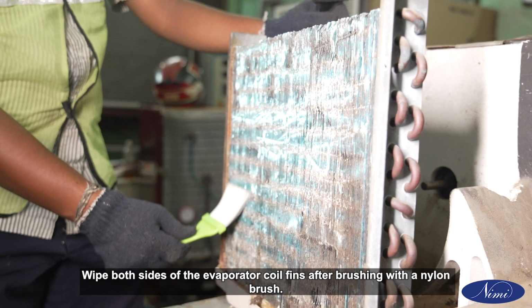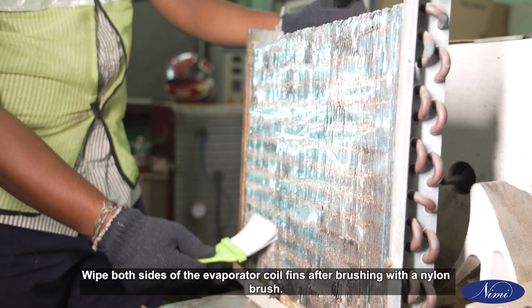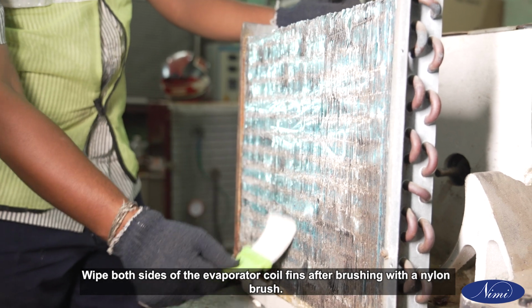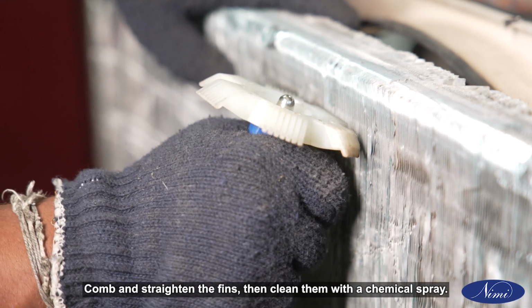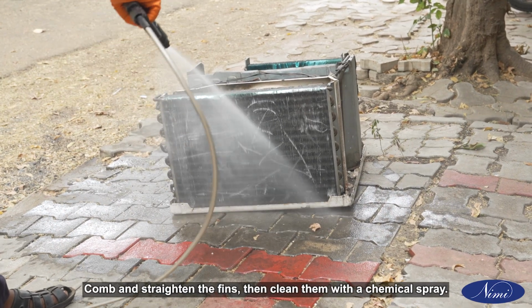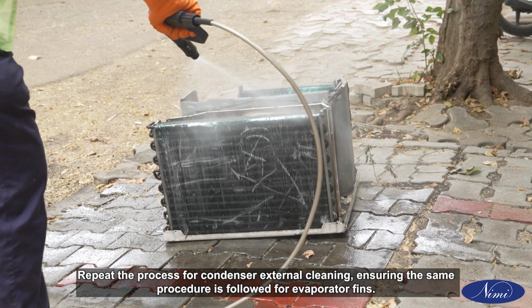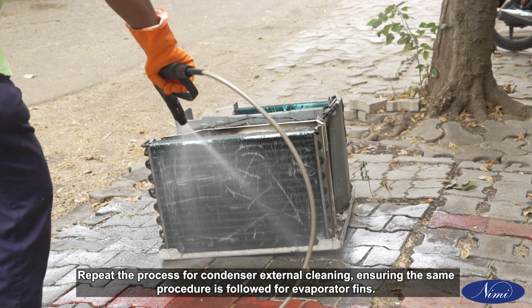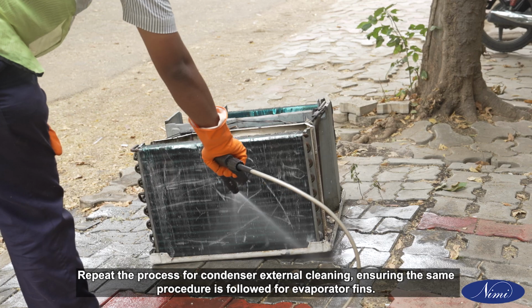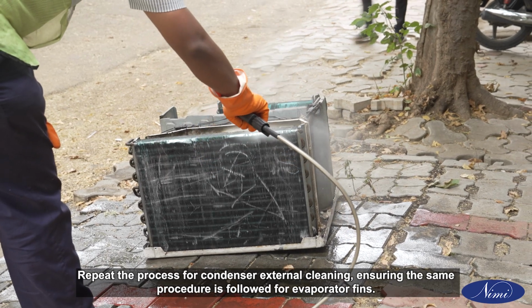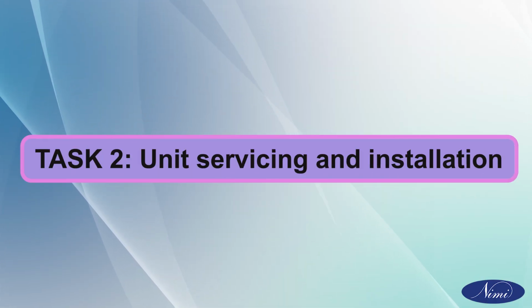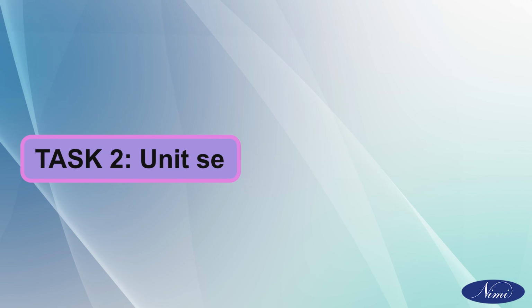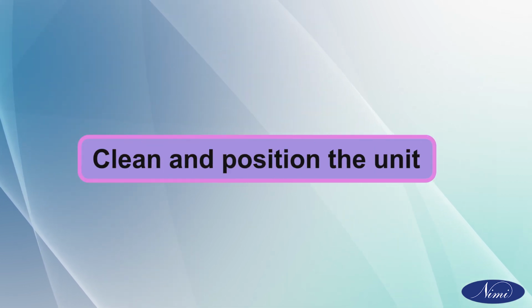Wipe both sides of the evaporator coil fins after brushing with a nylon brush. Comb and straighten the fins, then clean them with a chemical spray. Repeat the process for condenser external cleaning, ensuring the same procedure is followed for evaporator fins. Task 2. Unit servicing and installation. Clean and position the unit.